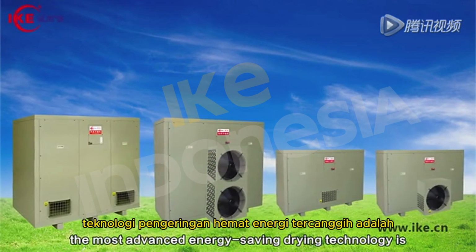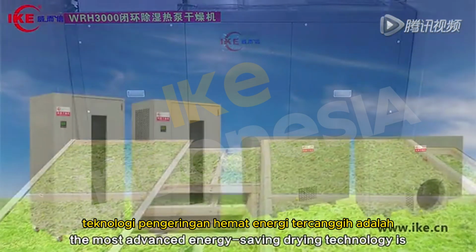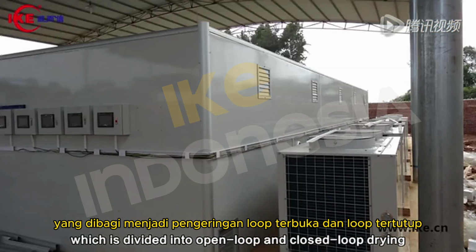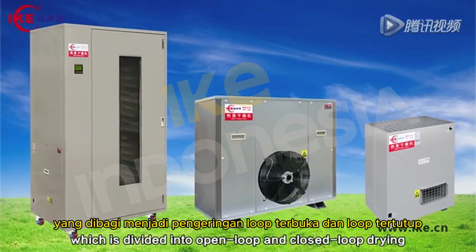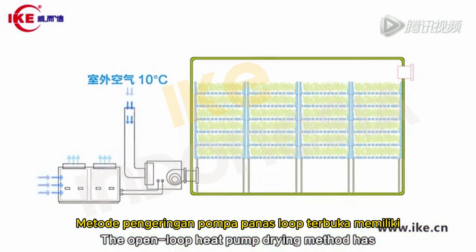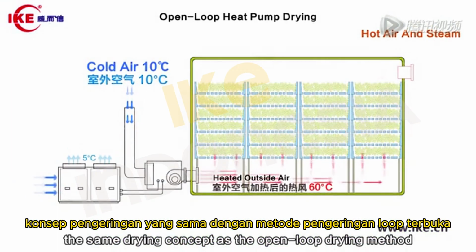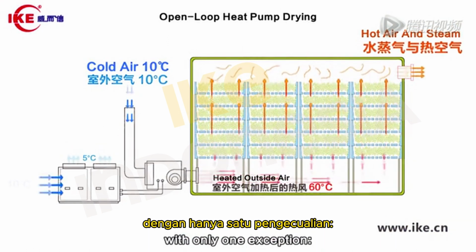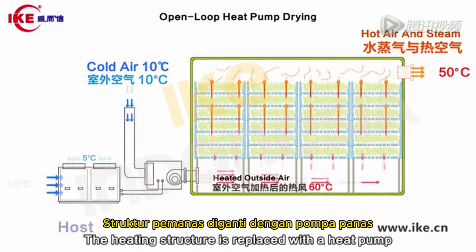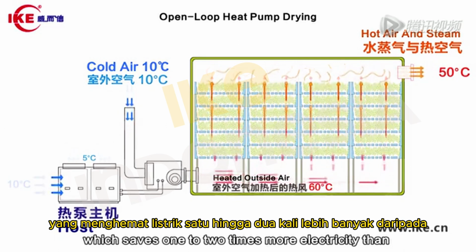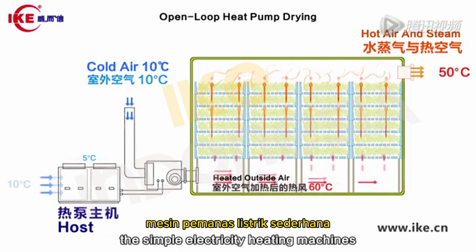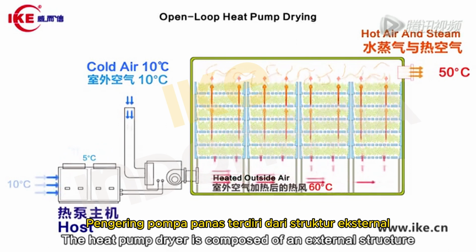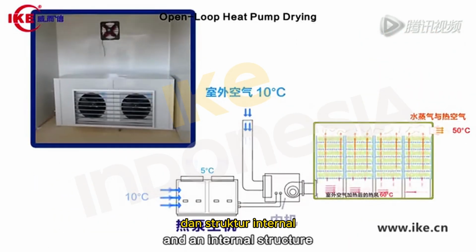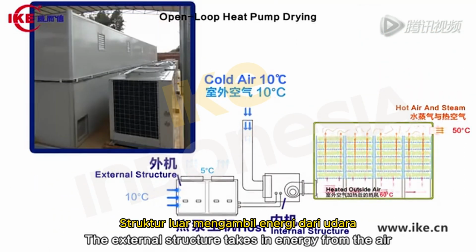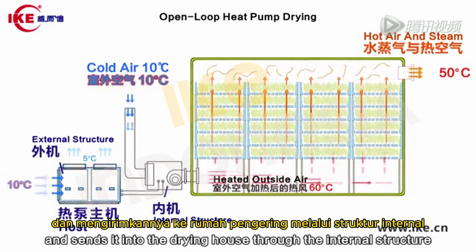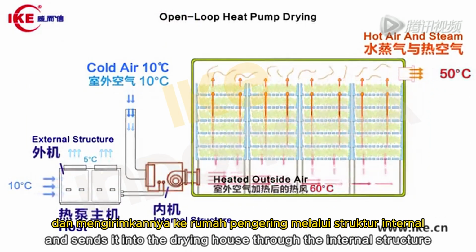At the present, the most advanced energy-saving drying technology is heat pump drying, which is divided into open-loop and closed-loop drying. The open-loop heat pump drying method has the same drying concept as the open-loop drying method, with only one exception: the heating structure is replaced with the heat pump, which saves 1 to 2 times more electricity than the simple electricity heating machines. The heat pump dryer is composed of an external structure and an internal structure. The external structure takes in energy from the air and sends it into the drying house through the internal structure.